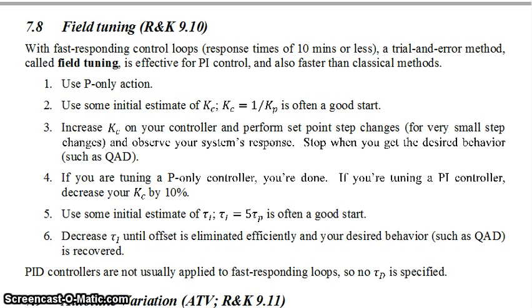If you're out in the field and you have a system that responds very quickly, response times on the order of 10 minutes or less, you can use this trial and error method called field tuning. This is effective for PI control and faster than the two previous methods we talked about. It's faster than Ziegler-Nichols. Cohen-Coon is fine as long as you have a first order plus dead time model.